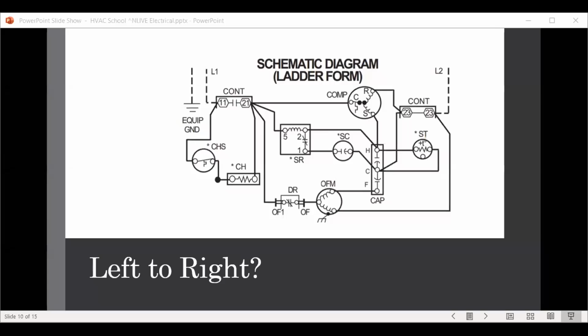But it was something that was interesting because most guys walked up to the unit and said, "Oh, fine, all the voltages are good," when the unit is running standalone. But when on automation, and they always blamed it on the automation to a certain extent, they didn't check all the voltages and see what was truly going on with the unit. That's actually a really good point.